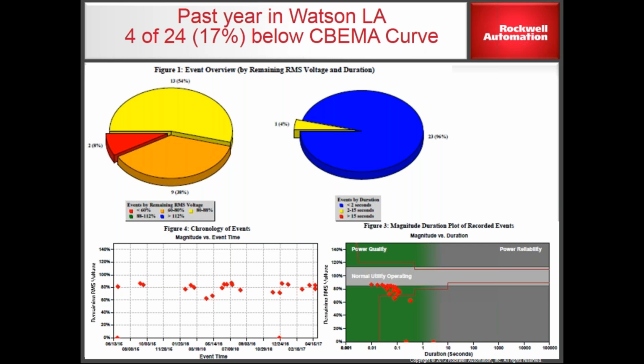The magnitude duration chart in the lower right-hand corner is really a picture of how low it went and how long it lasted. We're looking at the worst case for each event. Every diamond represents an event that had at least one phase drop to 60% remaining, lasting maybe 150 milliseconds. I don't know if all 3 phases did that, but I assume the worst case, so this is plotted assuming that worst case.